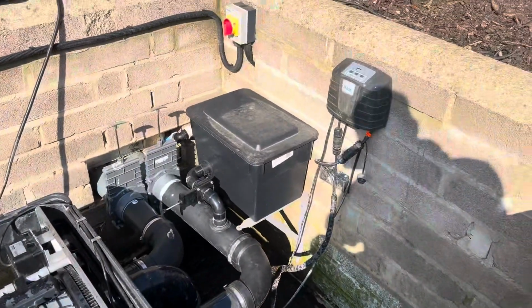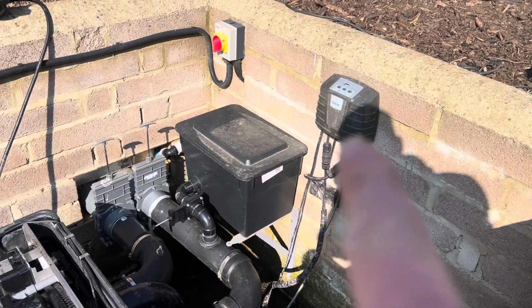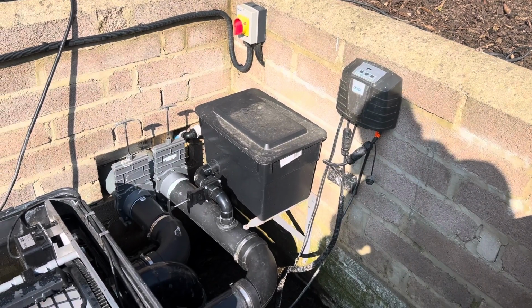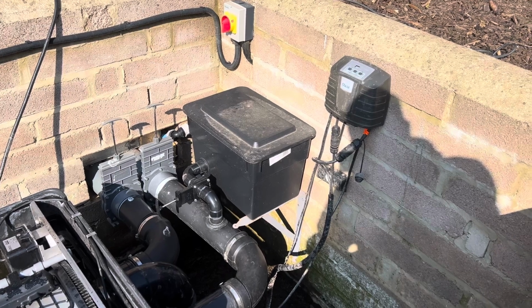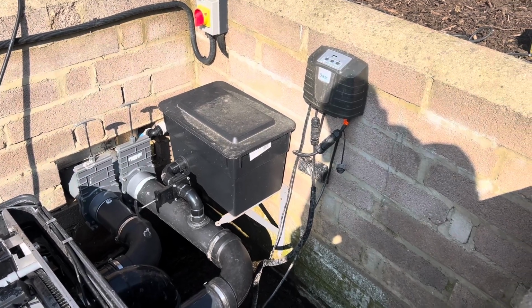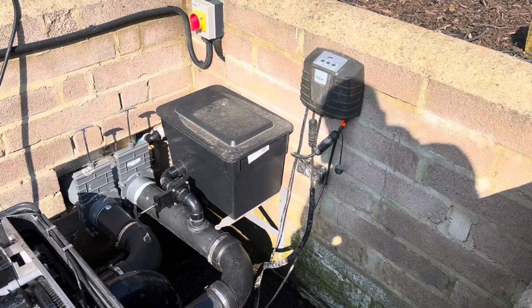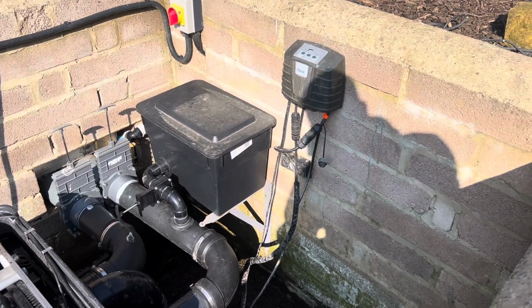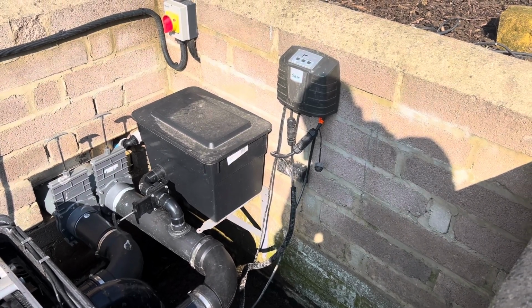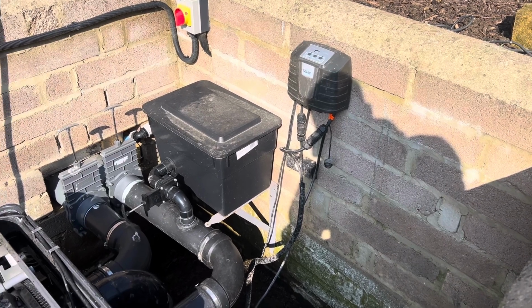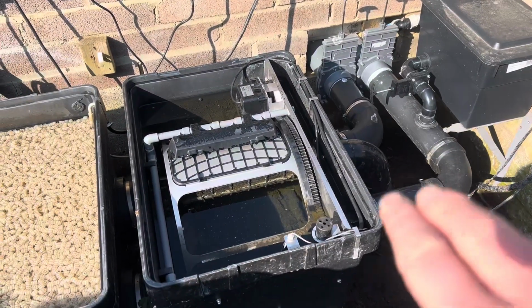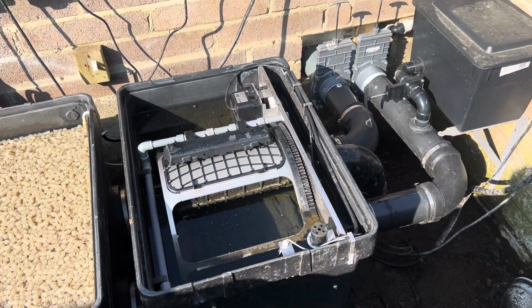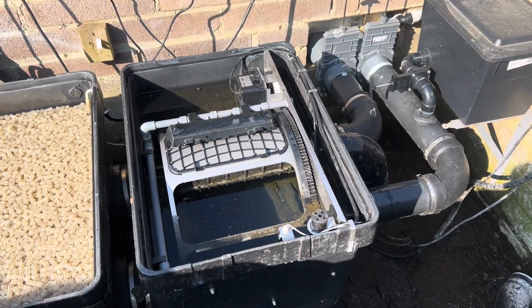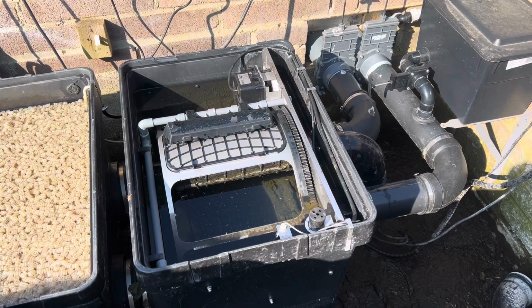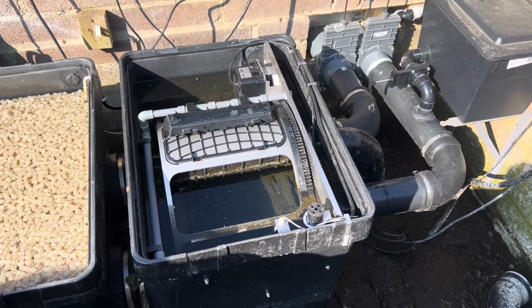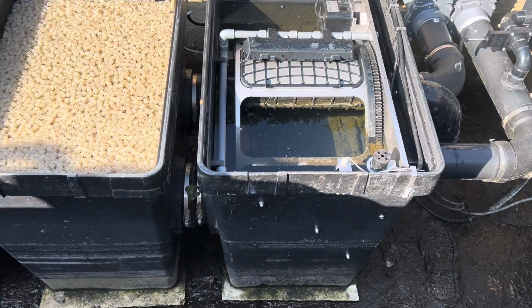What happened was, when that control panel was sitting down there, the connectors that you screw together to connect up the sensors were submerged underwater. So I actually think the product's done a great job, because considering it was virtually fully submerged underwater, we've just got to replace that sensor box that has the float sensors connected to it. So even though it has actually broken, I wouldn't put it down to a fault of the product - it was just a bad installation.